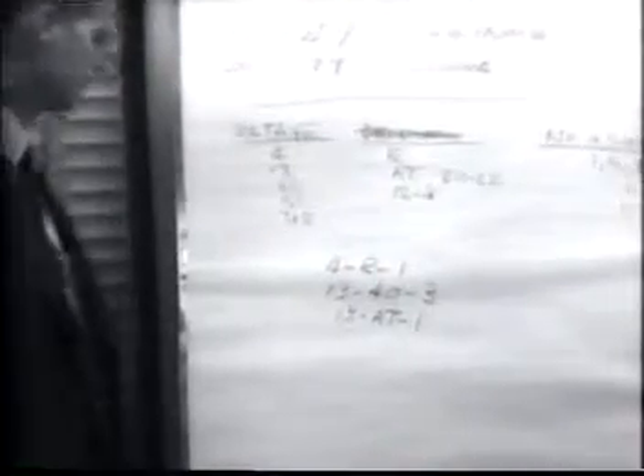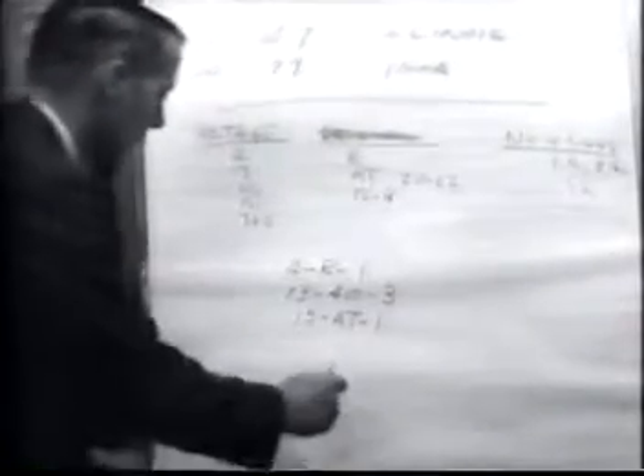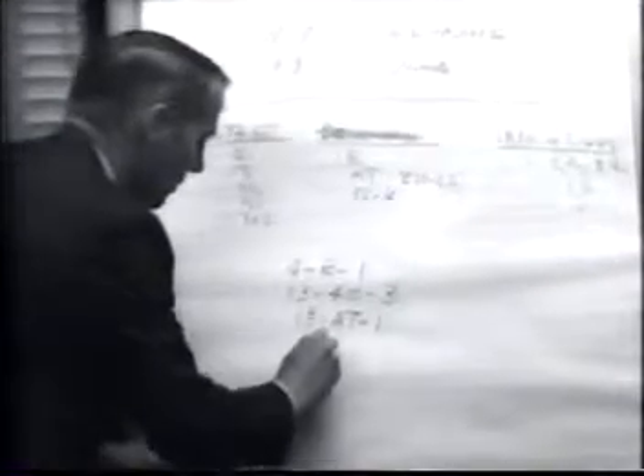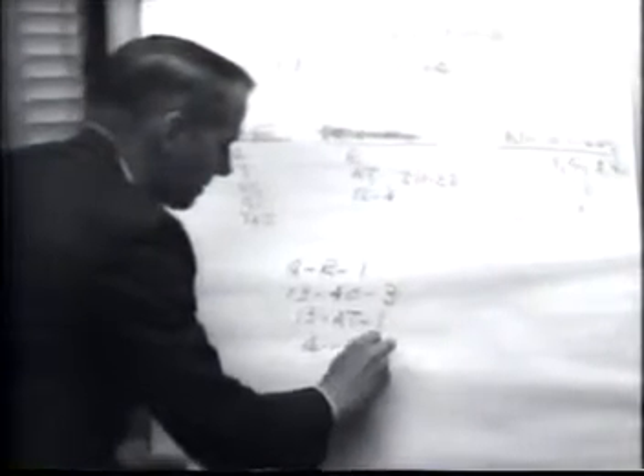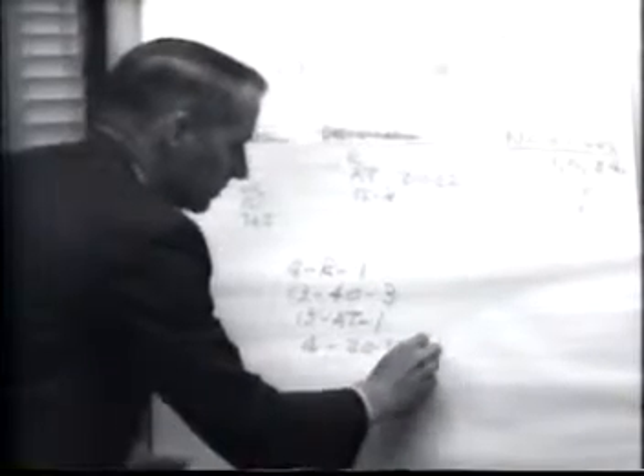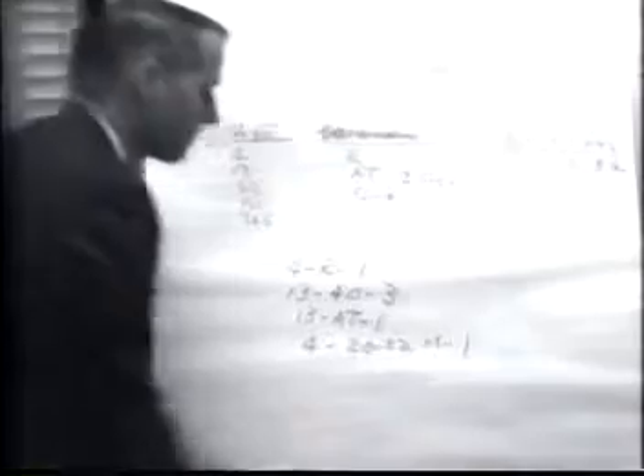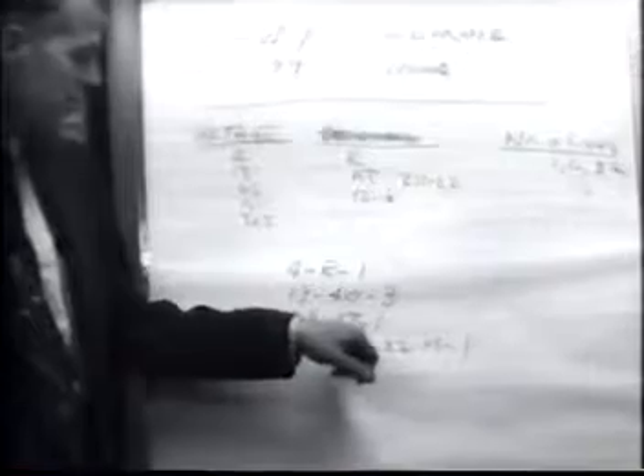We can also expand the substation identification in case we have a 3-terminal line, which happens with some regularity on our 4 kV circuits. Let's see if I can think of a good example. Well, I'll make one up. Say 4, 20, 22, M1. This would be a 3-terminal line with circuit breakers at subs 20, sub 22, and sub M. We do not use a substation terminology unless there's a circuit breaker at that point.